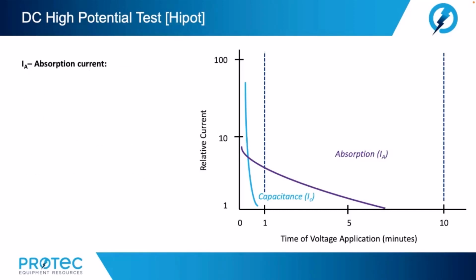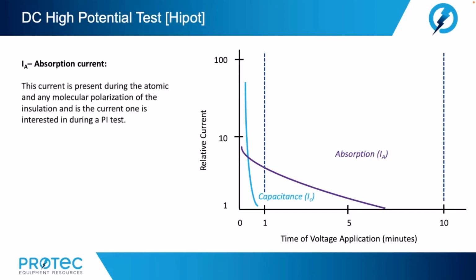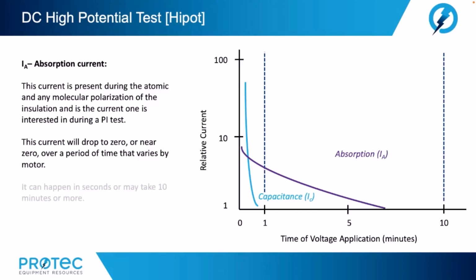And we also have that absorption current. This current is present during the atomic and molecular polarization of the insulation and is the current one is interested in during the PI test. This current will drop to zero or near zero over a period of time that varies by motor. It can happen in seconds or may take 10 minutes or more.